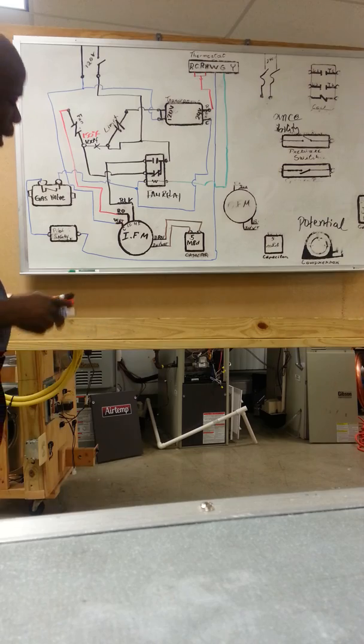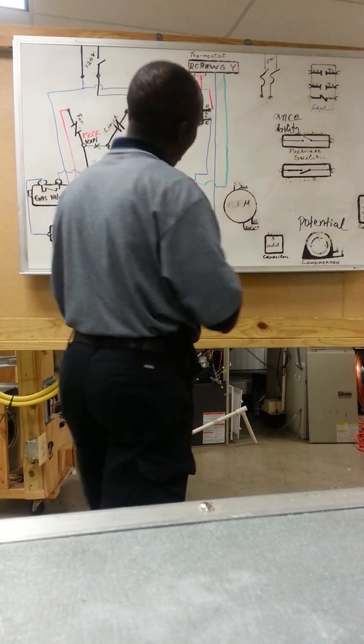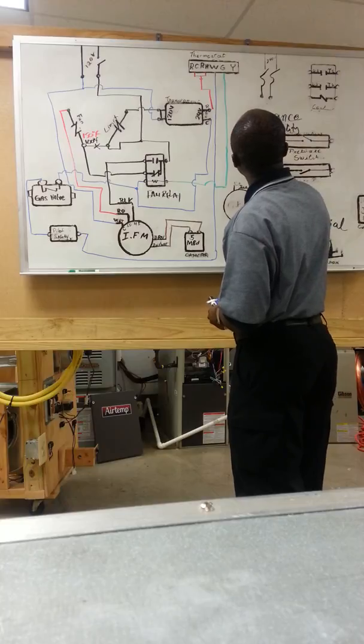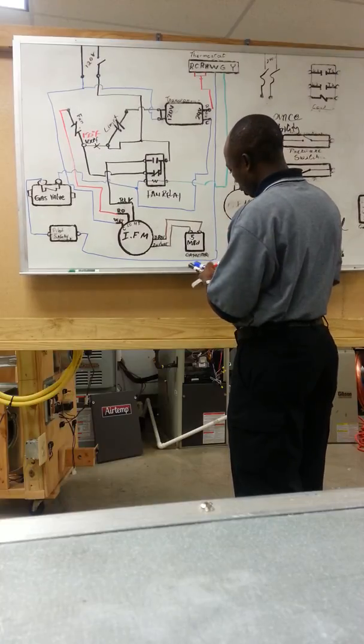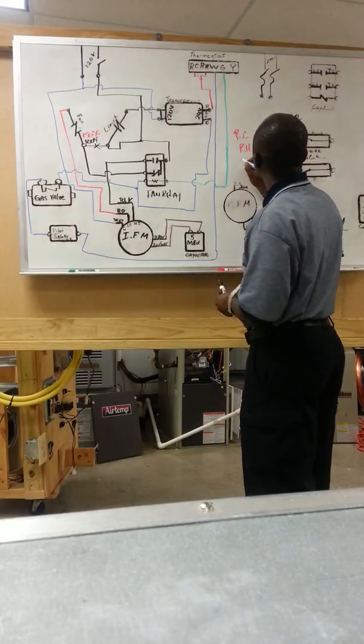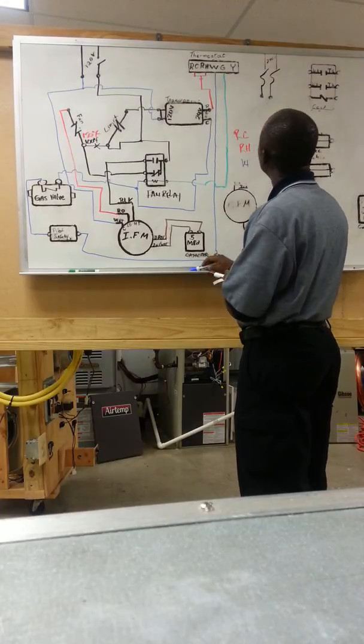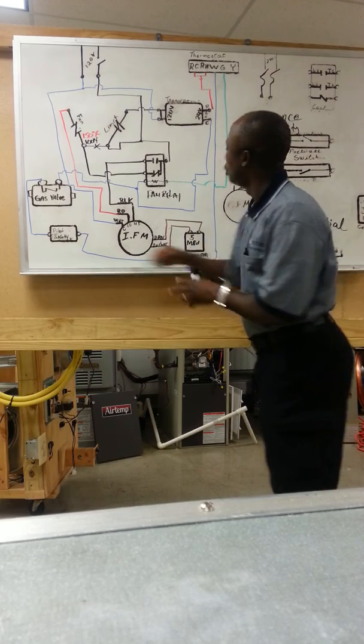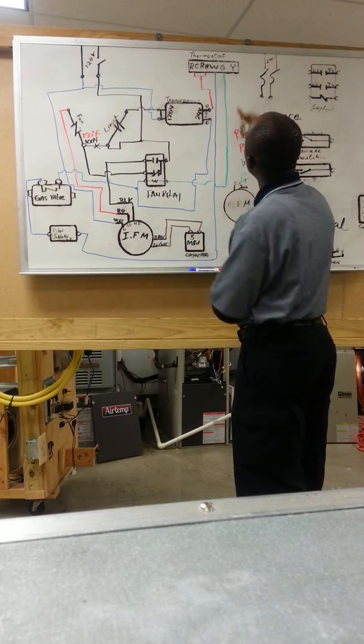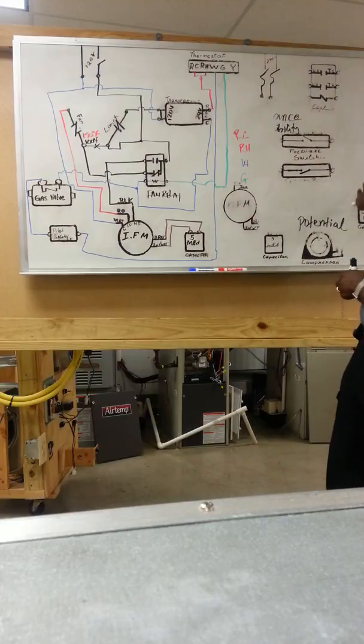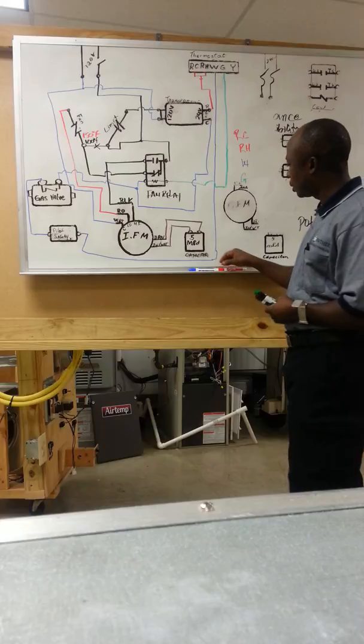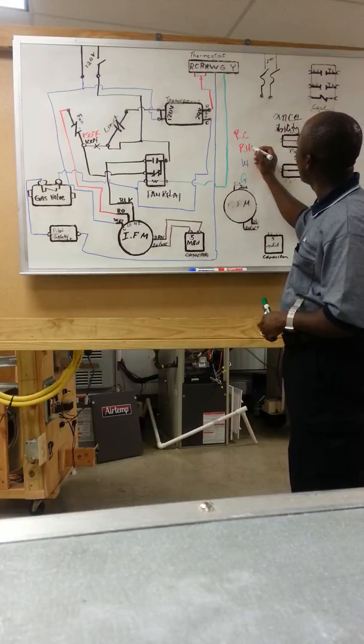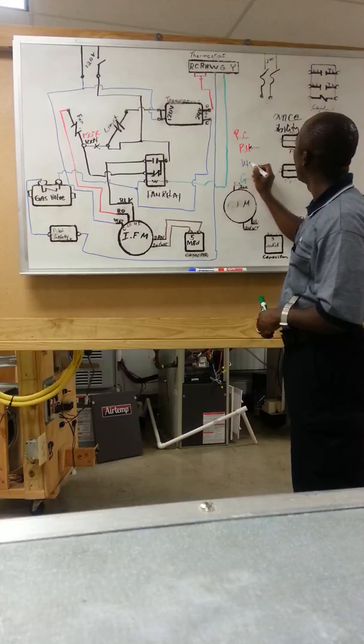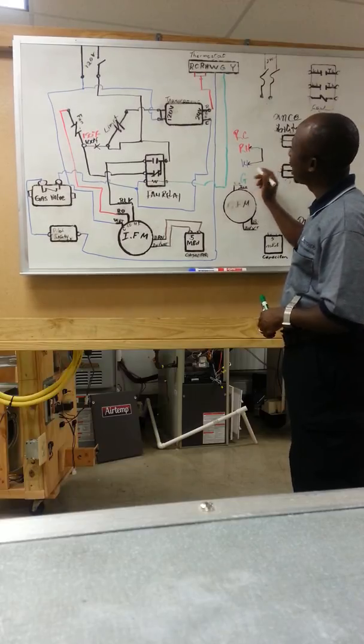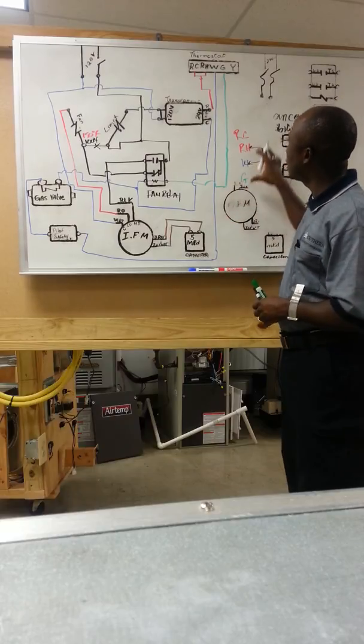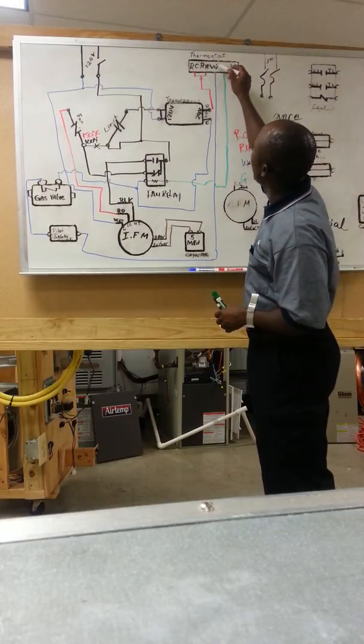Now once you call for heating, what happens on your thermostat? You have RC, RH, you have W, I'm going to use blue for white, you have G for green, I'm going to ignore yellow, that's for the cooling contact, so that will be on this part of the circuit. So once you call for heating, what happens? This contact here, the RH, which is 24 volts heating, and the W will close, and you hear a click in your thermostat. Once you hear that click, this is going to close. So what happens?